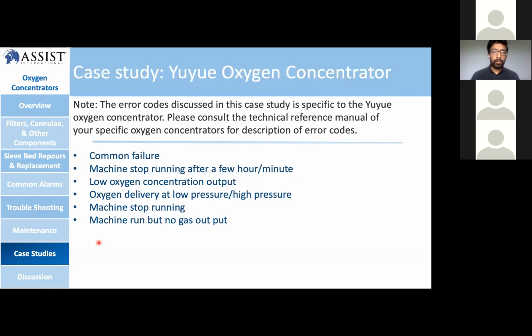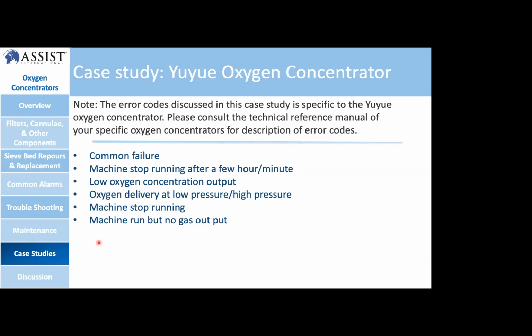The common problems we encounter during our maintenance activities are, first, the machine stops running after a few minutes. It starts, but it stops working after a minute or after an hour. This is the main problem we encounter during our activities. The second common failure is low oxygen concentration at output. Normally we face this problem in all oxygen concentrators we receive from the hospital, because another problem causes the output to be low in oxygen concentration. The other one is oxygen delivery at low pressure and or at high pressure.